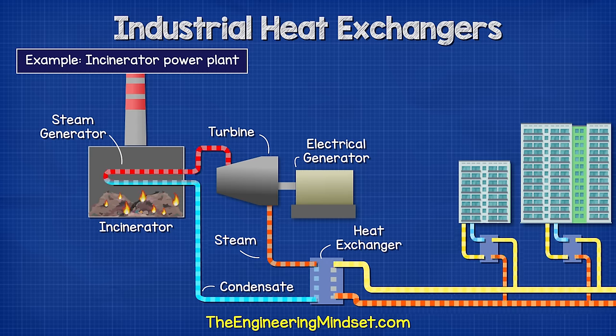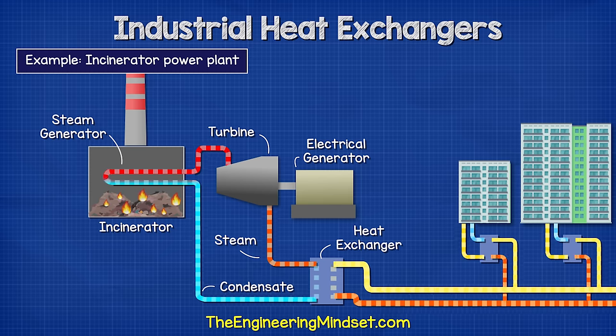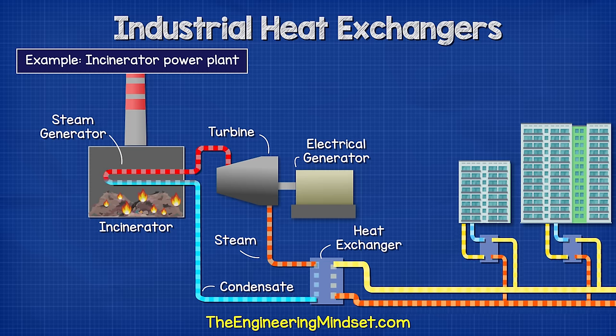These heat exchangers are very common for heating and cooling. For example, an incinerator power plant burns household waste to generate heat, creating steam that drives a turbine and generates electricity. The waste thermal energy then passes through a plate heat exchanger to heat a district heating network, and other buildings connect to this heat network also via a plate heat exchanger to supply their own heating demands — instead of operating their own individual boiler.